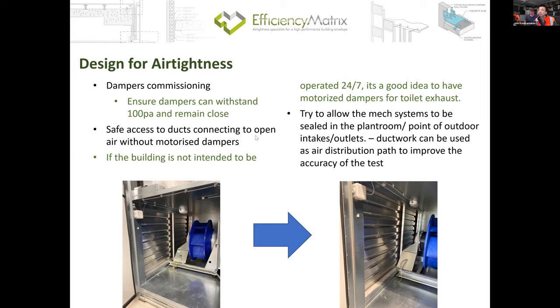When the commissioning agents are commissioning the dampers, make sure they put extra force into the actuator. Quite often we visually check the dampers and they look nicely shut, but as soon as we start the fan, they turn slightly open, which may not look like much, but imagine in a building you have 36 air handlers, each blade of the damper has a 3 mil gap. It adds up to a pretty big hole quite quickly.